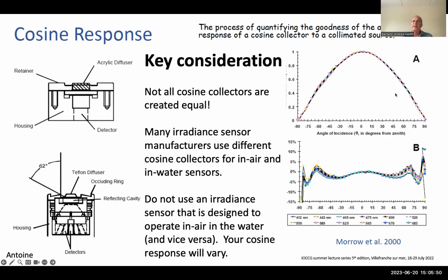Typically, one of the things looked at for how good the cosine response is, is you just look at this normalized cosine response from the measurement you made versus a true cosine response, or a true cosine factor. And then you look at the difference between those two. And typically what you see is it does pretty well. It's usually 1 to 2% maybe error across most, up to like 45 degrees plus or minus, but then it starts to break down again because of these edge effects. It's really hard to get those really high angles from literally 60 to 90 degrees without a huge amount of error coming into the system. Typically, you may see 5 to 10% error in the cosine response above 60 to 90 degrees, but less than 1 to 2%, usually between 0 and 30 degrees.